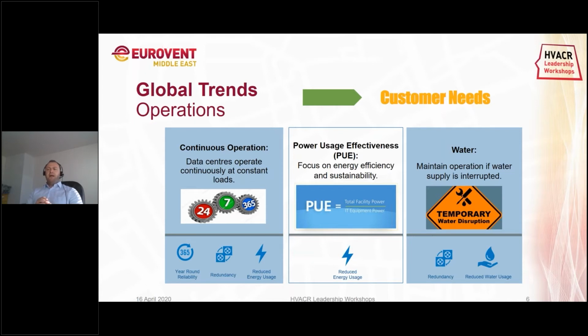In respect to that, there is a key parameter for data centers, and that's called PUE. PUE is the power usage effectiveness. It is the total facility power compared to the IT power, so the power that goes to the servers. The lower the PUE, the more efficient your data center is. You will see in Europe PUEs of 1.2, and we know that the average last year was 1.7. But we see also for older data centers that they go higher, like 2.0, even 3 or 4. So it depends on the date of construction, but there are also a lot of other factors that have a big influence on your PUE.